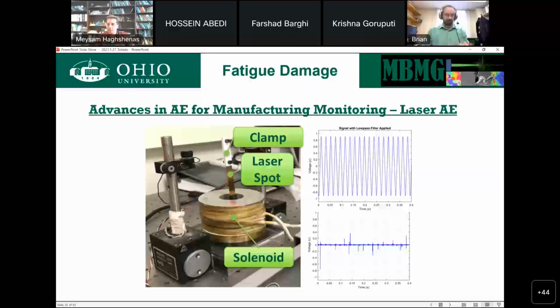The only other issue with ultrasonic, I want to emphasize a difference in one of our methodologies: with ultrasonic fatigue you have to design a very specific geometry because your sample is resonating. The methodology we're pursuing is actually building a spring that's going to resonate and treat the sample as a rigid body, so we can alter the geometry. The downside is right now we can hit 1500 hertz, 1.5 kilohertz. We can't hit 20 kilohertz from that, but it gives us ability to do different geometries.